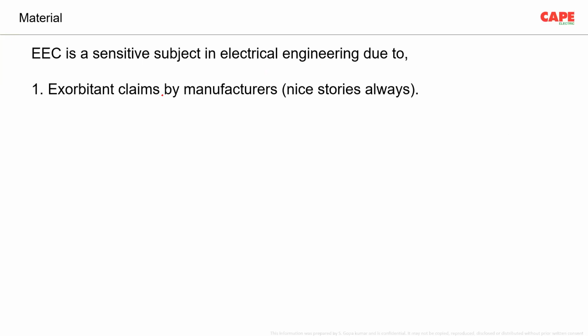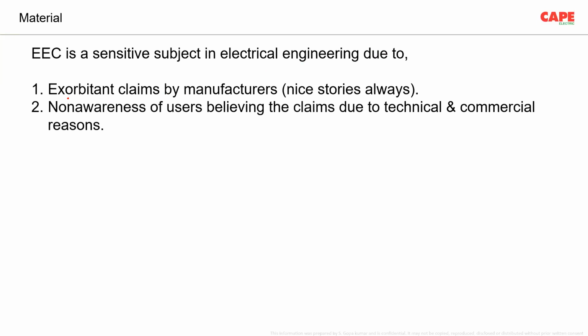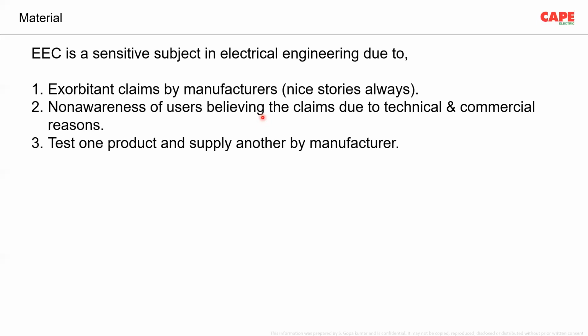Unfortunately, these are only claims. So problem number one is the exorbitant claims of the manufacturer. Number two, non-awareness of the users, believing the claims due to technical and commercial reasons. Technical reasons, for example: most of the time, there is a fault or damage to the electronics, and the safety engineer or the person, say for example, you have a UPS that has failed. The UPS vendor will come and say, sir, it is due to the higher resistance of the earth electrode, so you have to have an earth electrode of 1 ohm. It's a technical reason. Now, the client always tries to reach 1 ohm. Technically, this is wrong. So such non-awareness is one of the reasons.